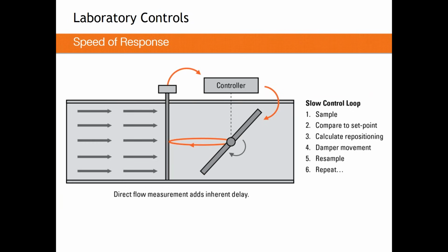Meaning, if you look between point number 3 and point number 4, from the time you calculate where to go and the time you start to go there, controllers can do that portion of the calculation very, very quickly. It can happen nearly instantly, in much less than a second. So for high accuracy terminals, they do have a high speed of response to that control signal. They start to move very, very quickly.